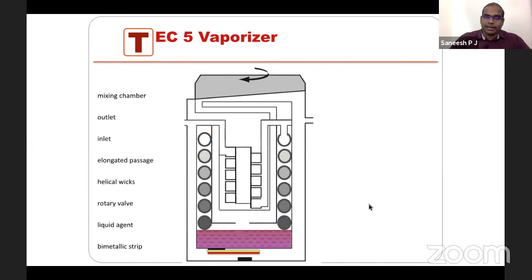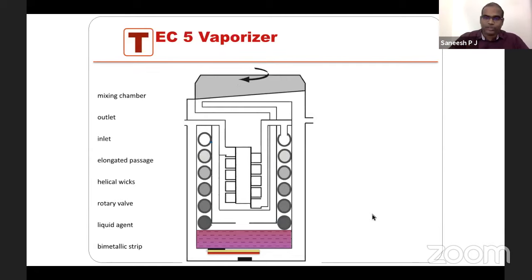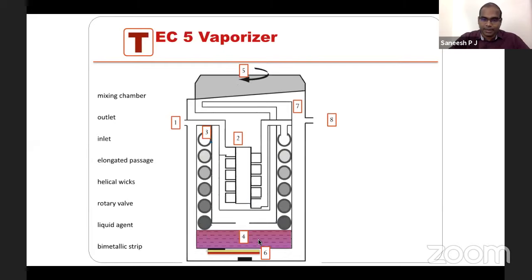The Tec 5 vaporizer: it is flow over, has wicks to maintain maximal saturation, variable bypass for regulation of output concentration, automatic thermocompensation via bimetallic strip at the bottom, agent specific for isoflurane, a plenum vaporizer, and vaporizer out of circuit. Looking at how the Tec 5 works: you can identify the vaporizer inlet, the elongated passage called the IPPV assembly, the helical wicks, the liquid vaporized agent, and the rotary valve.